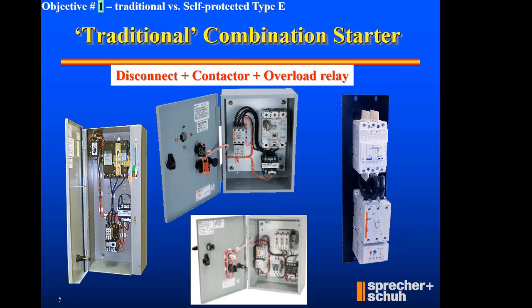Initially, starting out on objective number 1, let's establish what's a traditional versus self-protected type E. On the screen I've given you some visuals. Pictures are always nice. From a traditional sense, I've got a disconnect, some sort of a disconnect, plus a contactor, plus an overload relay. So I've got 3 components.